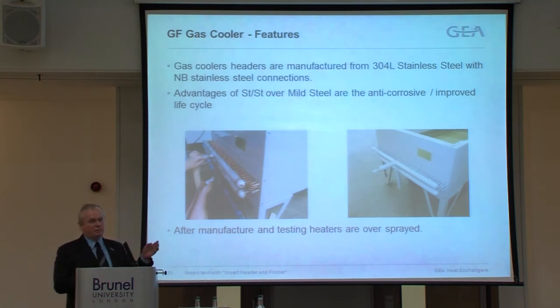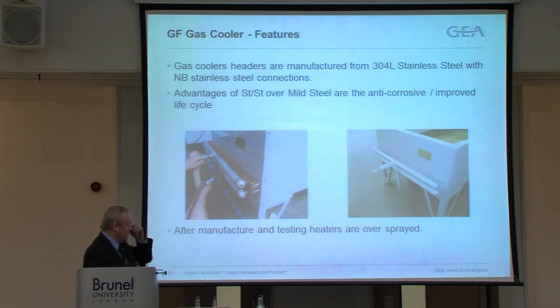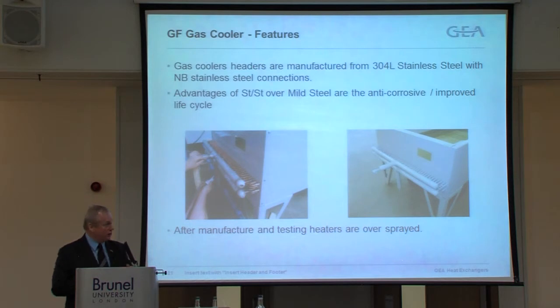We were finding that brazing an 8mm diameter tube to a large header, we just got the header too hot, and we rejected K65, although I understand we're now going back to look at it. What we ended up with was a stainless steel header with proprietary caps, stainless steel connections, and all of the 8mm tubes that go into the matrix are actually stainless steel. We then spray it afterwards, but we identified that as a possible corrosion point, so stainless steel is not going to rust in the future.